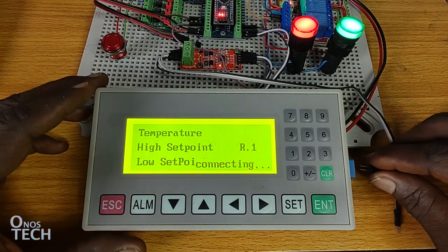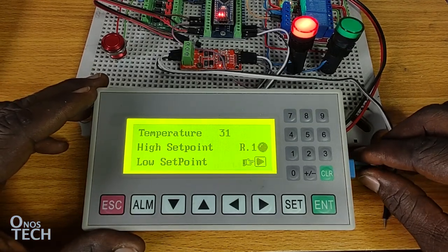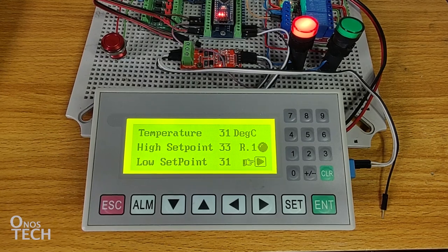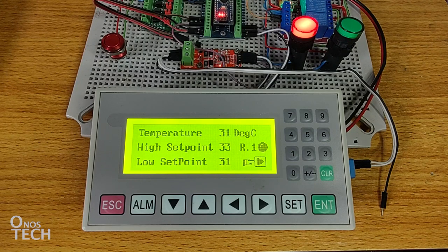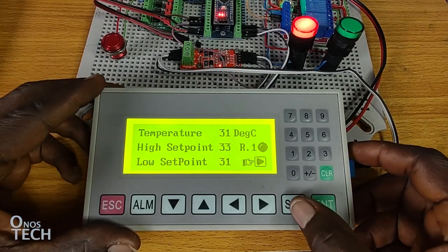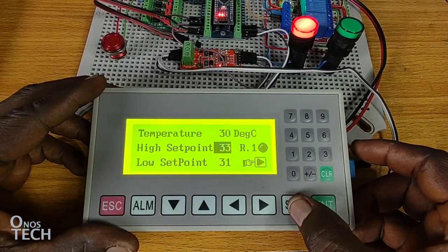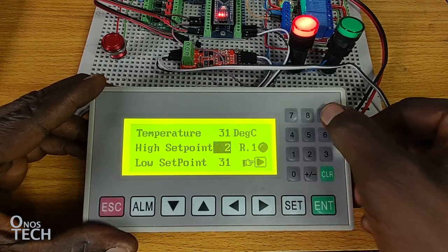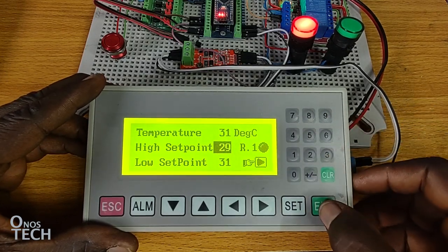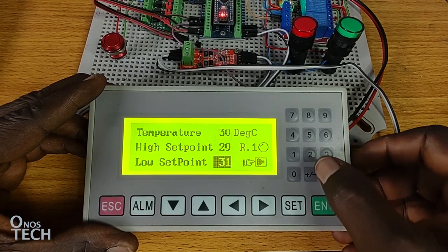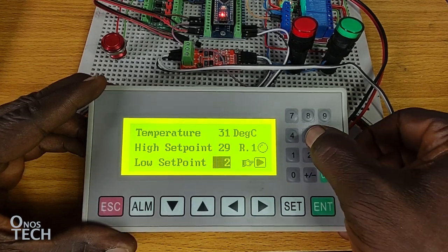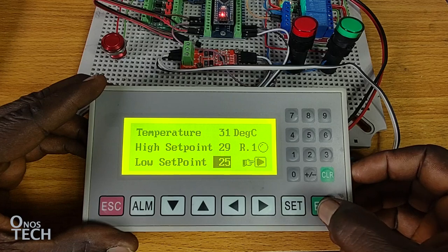Now connect terminal B of the TTL to RS485 module to pin 8 of the panel DB9 connector and terminal A to pin 9. Observe that the temperature value, the set points, and the lamp now appear on the screen. To change the set points, press the set button and input the required set point for the high set point. Then press the enter button. Change the low set point and press enter.